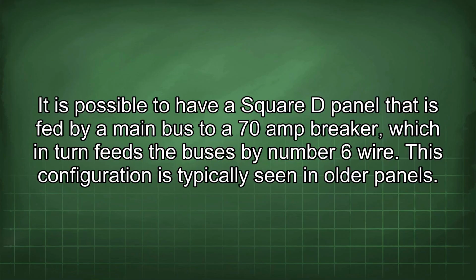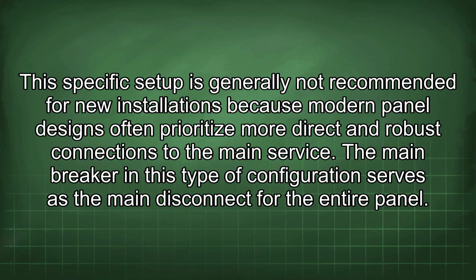It is possible to have a square D panel that is fed by a main bus to a 70-amp breaker, which in turn feeds the buses by number 6 wire. This configuration is typically seen in older panels. This specific setup is generally not recommended for new installations because modern panel designs often prioritize more direct and robust connections to the main service.